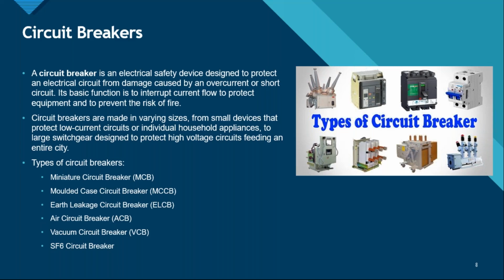You all basically know how MCBs work. If there is high current passing through, the MCB is going to trip. It is going to break the circuit, and you need to identify the fault. You need to rectify the fault, and you can switch on the MCB again, right? In a way, if you want to talk about it, a fuse is also one sort of an MCB, right? But when it comes to a fuse, if the fuse is tripped open, you need to replace the fuse. Whereas if you have a circuit breaker, you can just rectify the fault and switch on the circuit breaker back again.